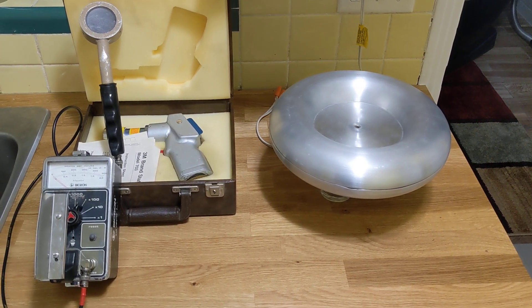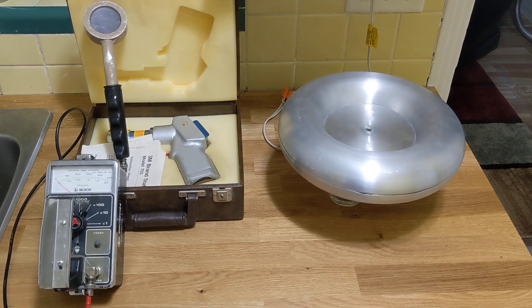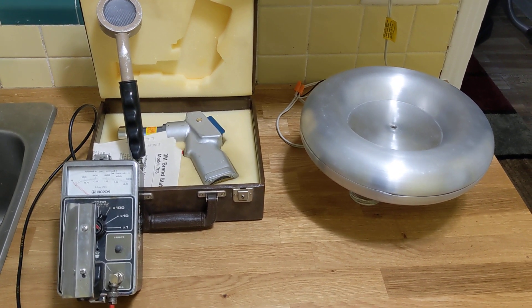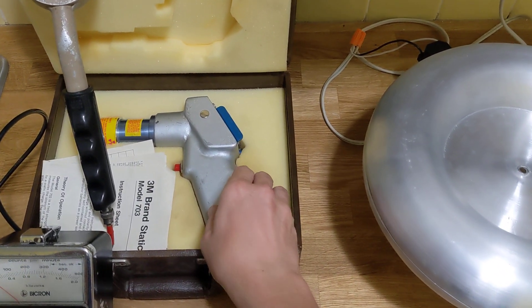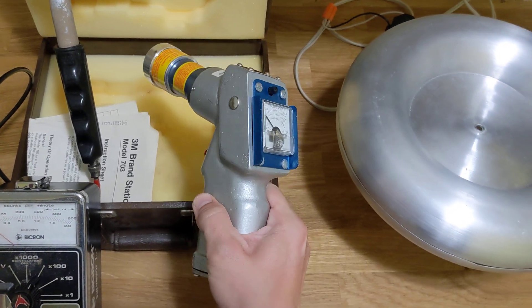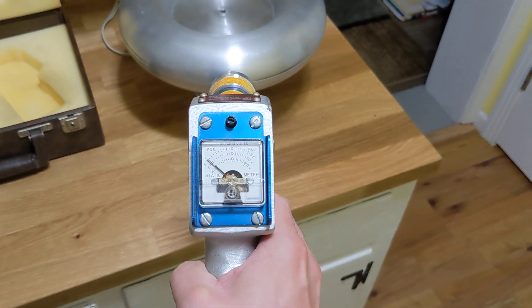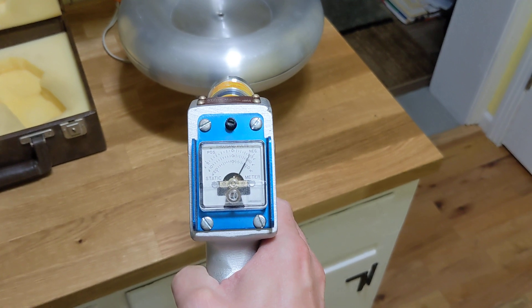Hello, Grant Trent here, and this evening I'm demonstrating what is at least a novelty to me, a 3M brand Model 703 Static Electricity Field Meter.